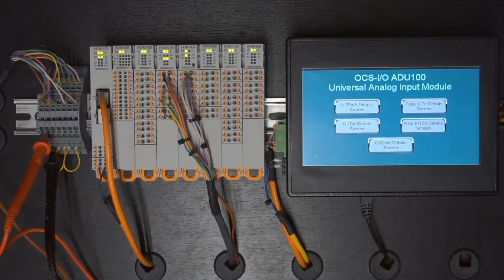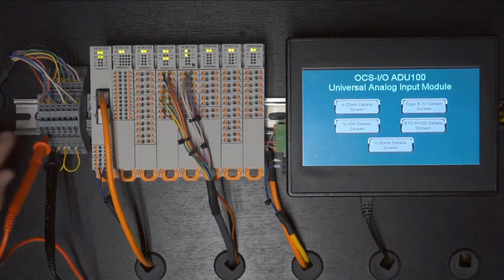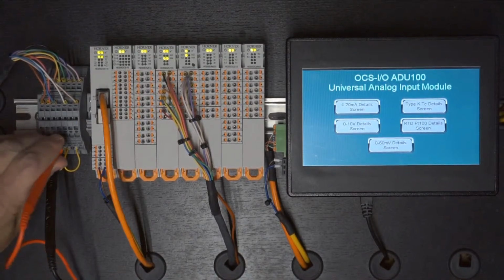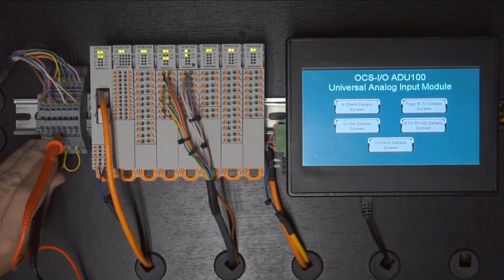So I'll disconnect my thermocouple probe here, and I'll change my simulator from thermocouple to RTD, which I have done. And we'll go with, say, a 50 degree setting. Of course, I've got to remember to move my probes. Okay, let's move them here.